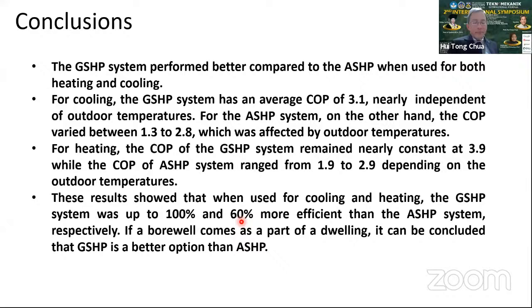If we compare the GSHP system, the ground system, with the air system, which is better for saving energy? It's certainly the GSHP, because you can see on this slide, for cooling, this is 1.3 versus 3.1. This 2.8 is when it is very near 25, 26 outdoor air temperature, by the way. So it's at times when it's not needed.